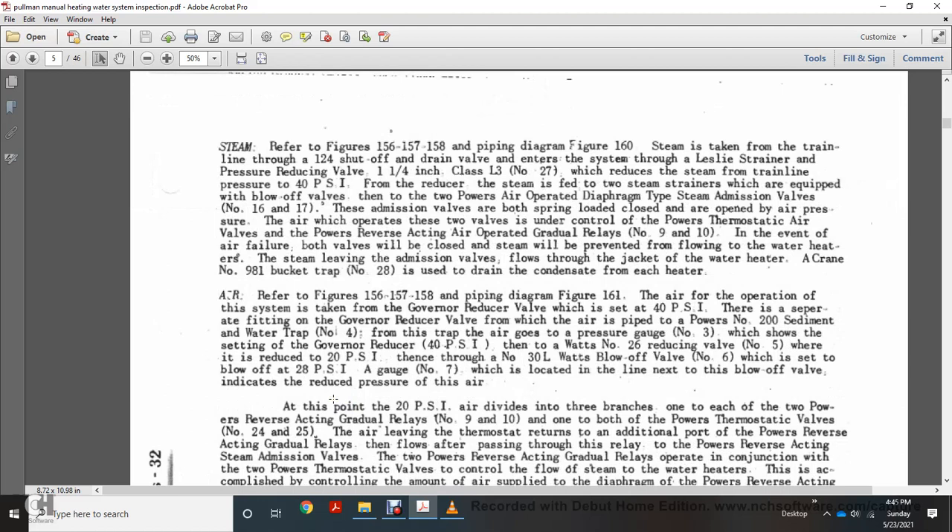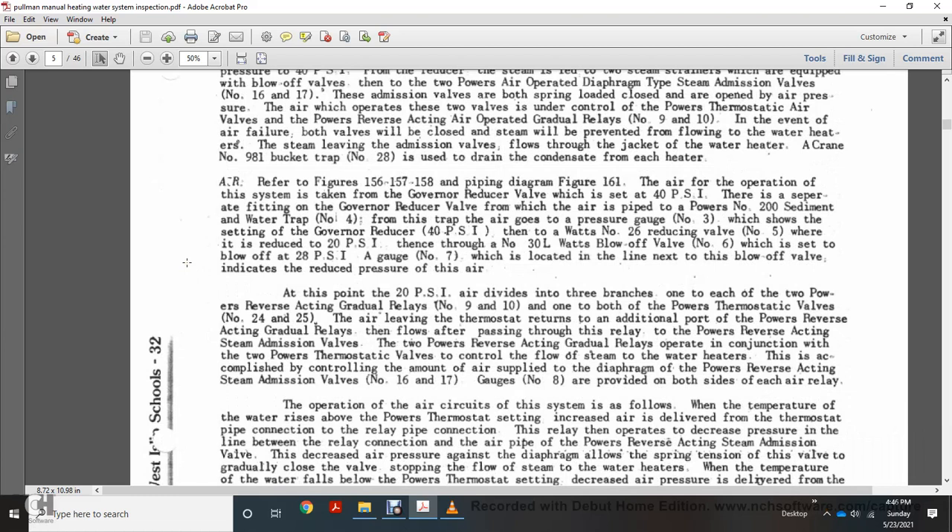Referring to figures 156, 157, and 158 piping diagrams: steam is taken from the train line through a shutoff and drain valve at the end of the system. It passes through a pressure reducing valve, one and one-quarter inch Class L3, number 27, which reduces steam from train line pressure to 40 psi. Steam then passes to two Powers air-operated diaphragm type steam admission valves numbers 16 and 17. These valves are spring-closed and air-pressure-operated; when air pressure fails, both valves close and prevent steam from flowing through the water heaters. Steam leaving the admission valve flows through the jacket of each water heater and through the Crane number 981 bucket trap number 28, which drains condensate from each heater.